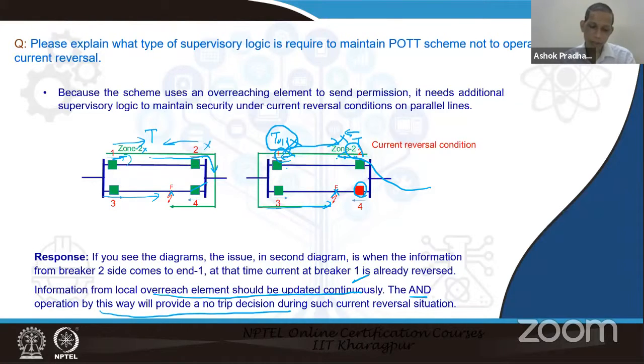Okay, sub-cycle tripping is avoided. What is the expected value of X by R during power swing, as circuit breaker operation depends upon this? Whatever it may be during power swing, there is no point of tripping. So I believe circuit breaker tripping is not the issue. If you are talking about out of step tripping, that is one issue, true. But normally the distance relays which we have have power swing blocking, and this is during normal swing, so the issue of fault clearance will not be there.